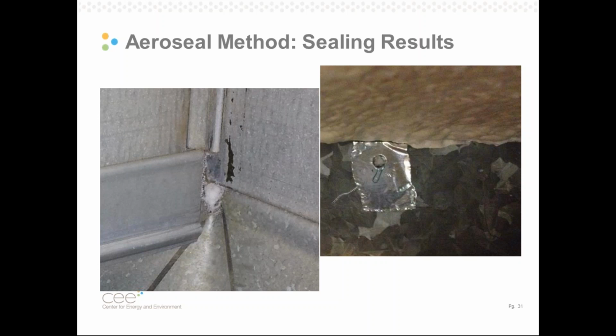So I have a few images of larger leaks where we can see the Aeroseal. On the left, we have a transition piece where a sheet metal worker was a little bit aggressive, and this resulted in a 3/8 inch gap right at the slip and drive joint. At the end of the Aeroseal process, this 3/8 inch hole was essentially filled with the Aeroseal product, and it is now a tight seal.